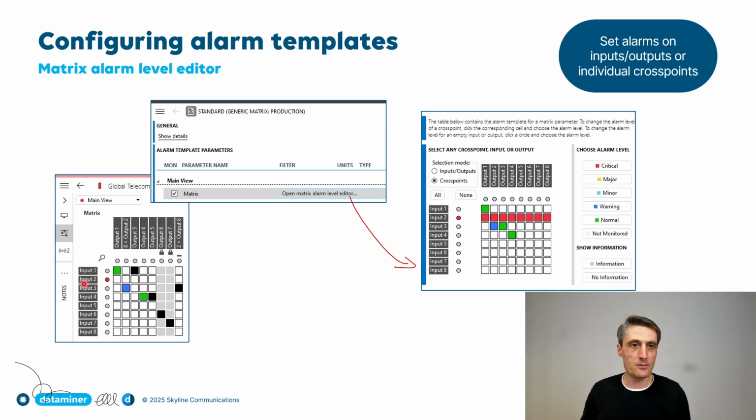In this case, we also have an alarming on the input 2, that input 2 is currently generating a critical alarm because nothing is connected to that. That's not good. If nothing is connected to that, we have a condition where we want to notify the operator. How does that work to define that? We'll see that it doesn't fit into those columns. So therefore you have in those columns just a special button that opens up the special control to make all the necessary thresholds in that special editor.